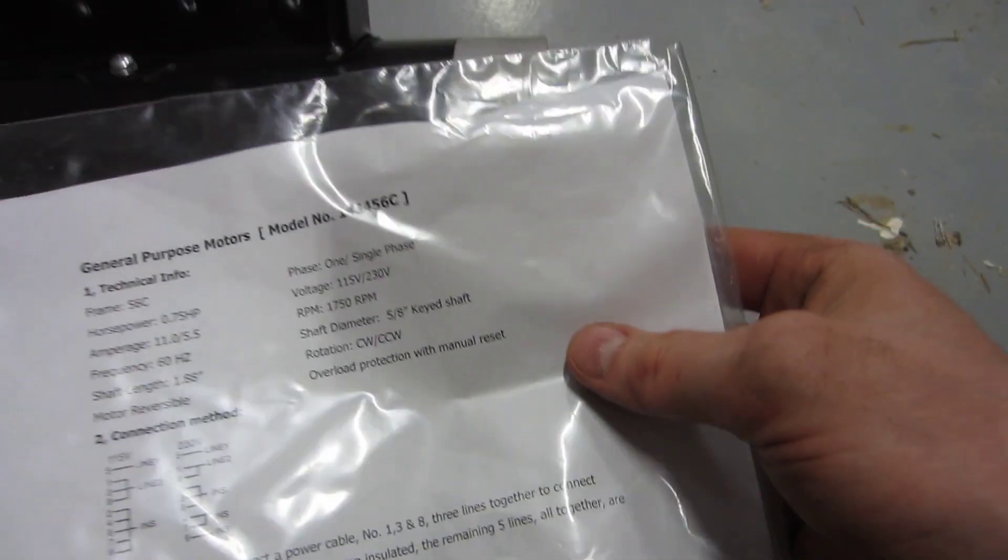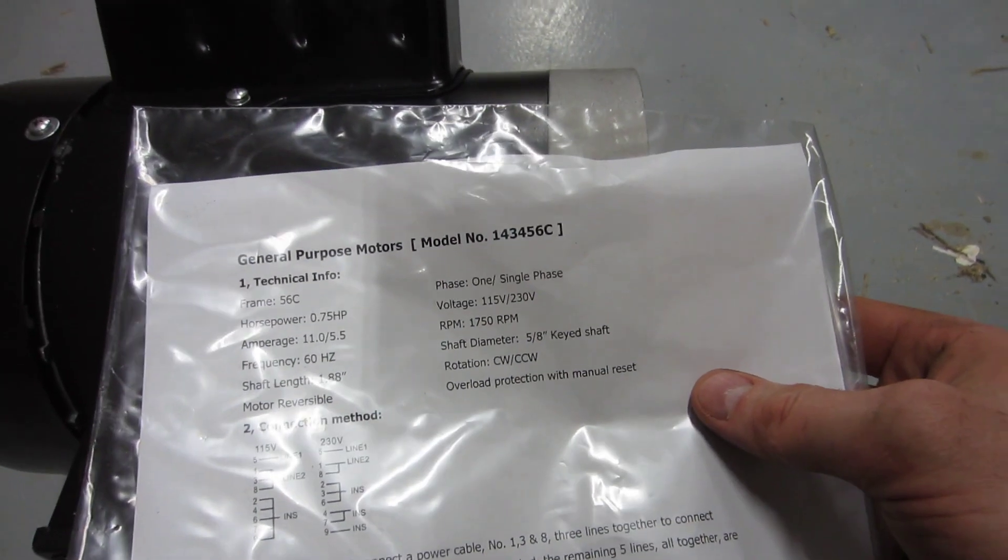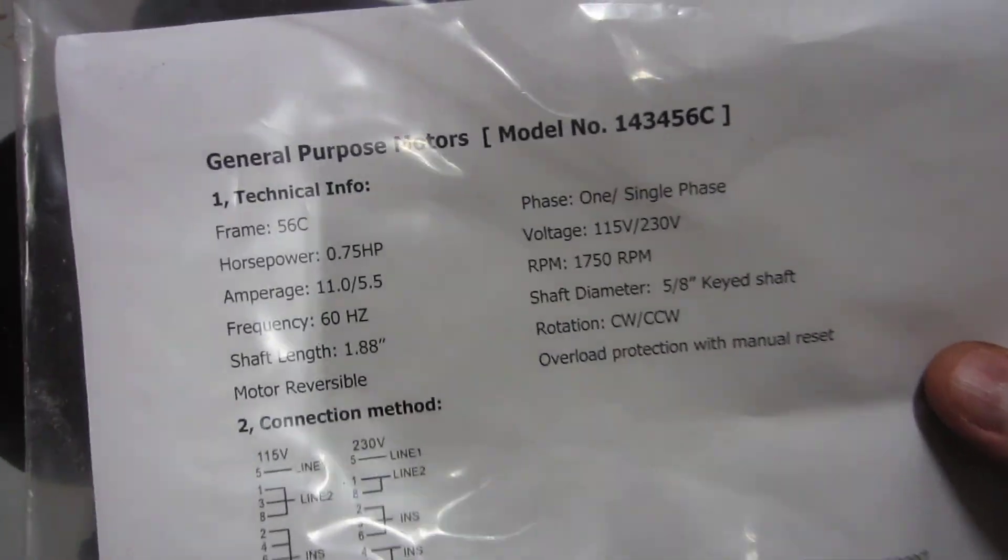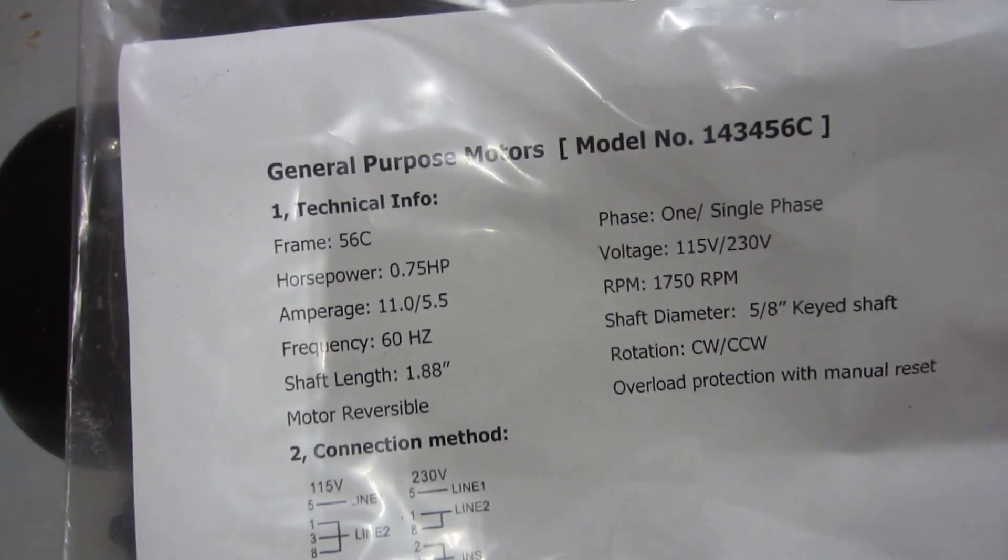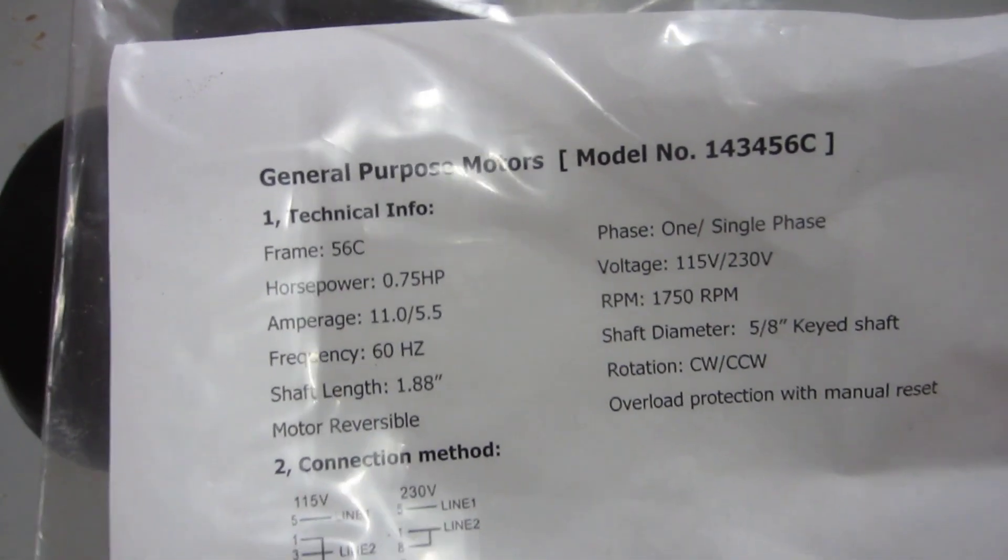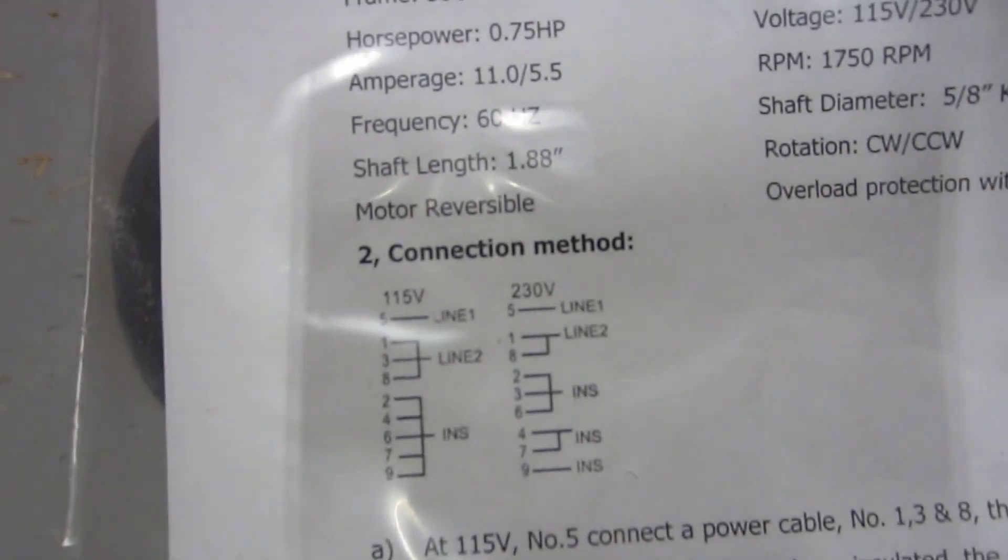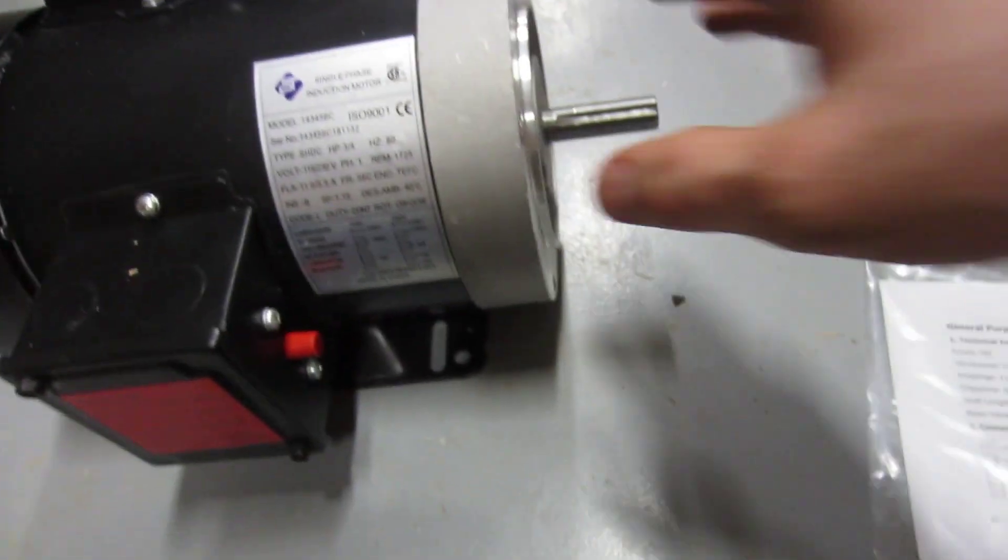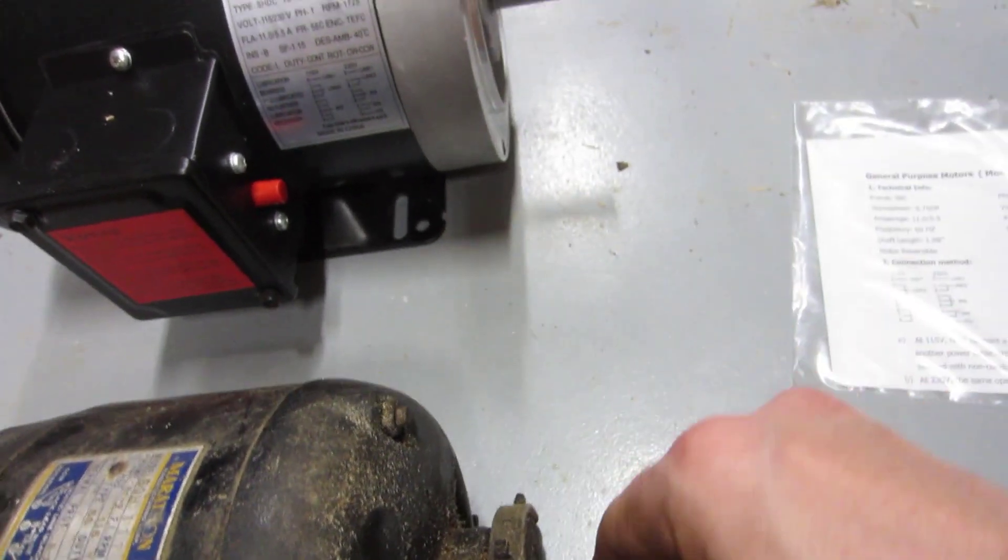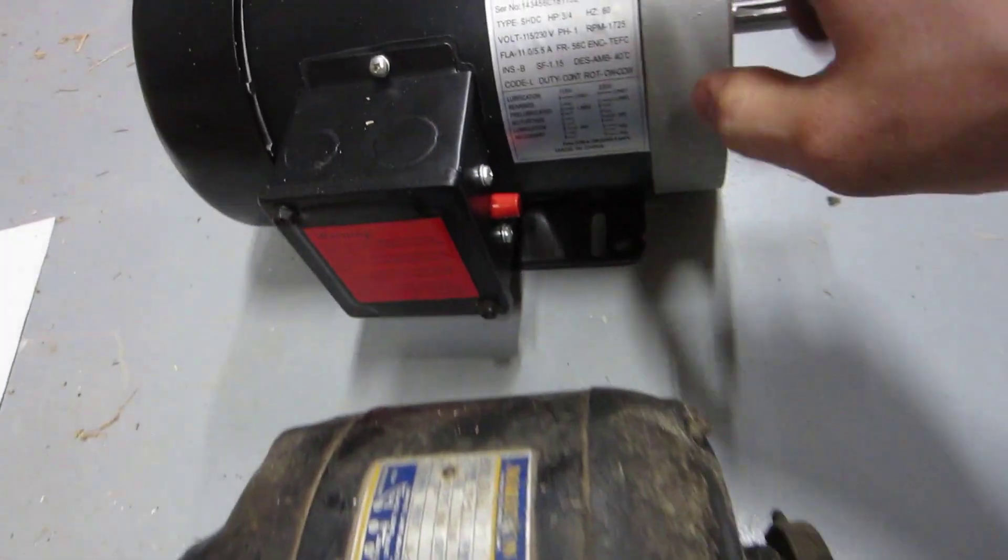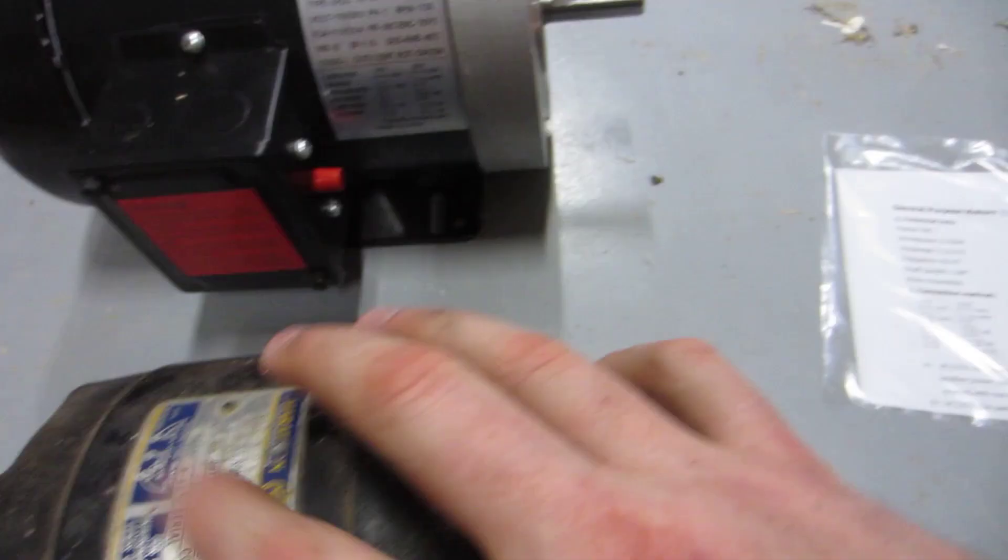It says all this stuff here. You can see the 115/230, it operates on both, and that's 11 amps on 115 or 5.5 on 230, 60 Hertz, etc. So this is a fully compatible motor other than it's 3/4 horse instead of 1/6.